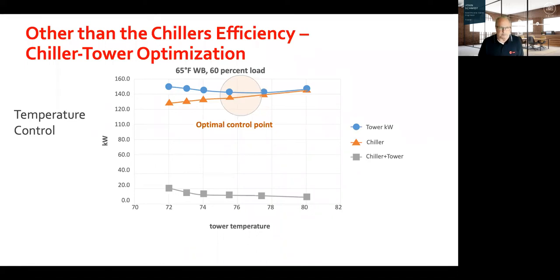So we'll look at the cooling towers, okay? Colder is not always better because as the cooling tower water changes, it can actually make the chiller less efficient. There's more lift or less lift on the chiller. So a lot of companies have chiller optimization programs. We have one ourselves that utilizes wet bulb, dry bulb, and goes through some pretty complicated algorithms.